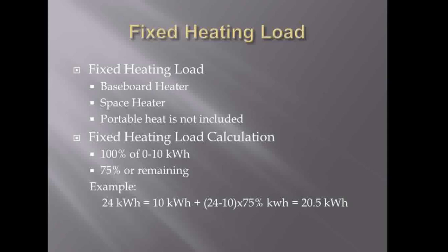Now let's move on to the fixed heating load. When we talk about fixed heating load, we mean baseboard heaters or space heaters — not portable heaters. A 1.5 kW portable heater in your bedroom doesn't count. For the fixed heating load calculation, we calculate 100% of the first 10 kilowatts, and 75% of the remaining. For example, if you have a 24 kW baseboard heating system, you take 100% of the first 10 kW plus (24 − 10) × 75% = 20.5 kW total.